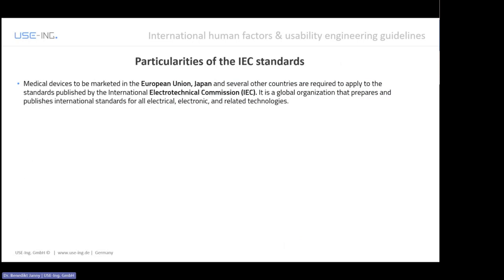So now I want to dig a little bit into the details of each guideline. We have this basic structure, the basic process that all of them have in common. But now let's jump into details. Medical devices to be marketed in the European Union and Japan and several other countries are required to apply the standards published by the International Electrotechnical Commission, the so-called IEC. It is a global organization that prepares and publishes international standards, basically for all electrical or electronic and related technologies.